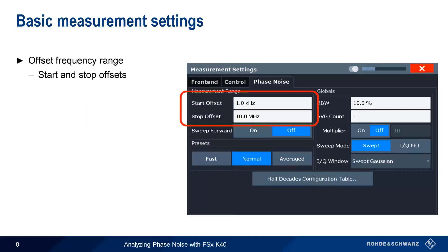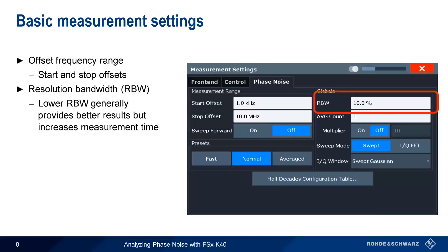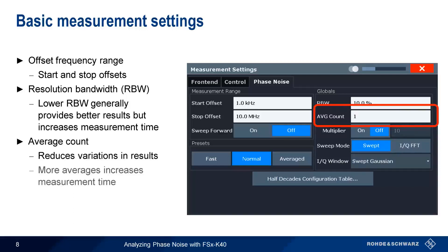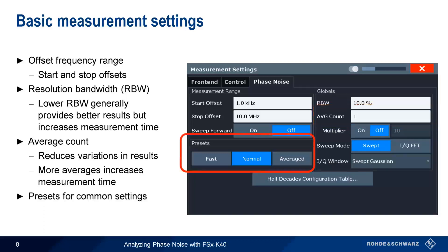After setting frequency and level, the next most important parameter is the offset range over which we measure the phase noise. This is defined using start and stop offsets, which determine the lower and upper bounds of the results plot. We can also specify the resolution bandwidth — a lower RBW generally provides better results but increases measurement time. Similarly, we can specify a number of averages, which reduces variation but also increases measurement time. Finally, a set of presets are available for common measurement tasks.